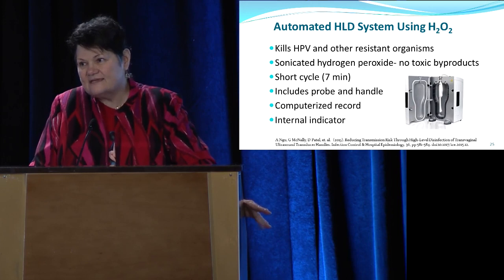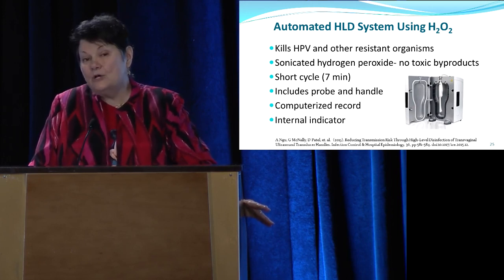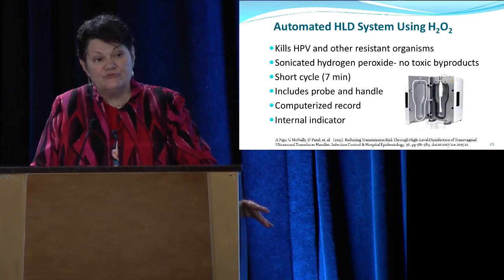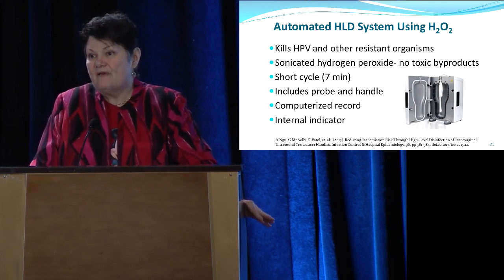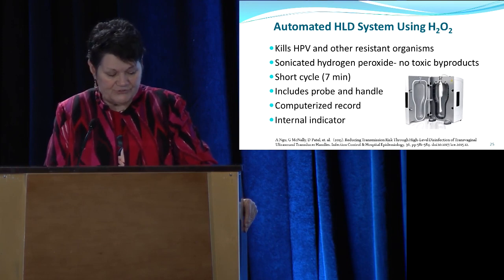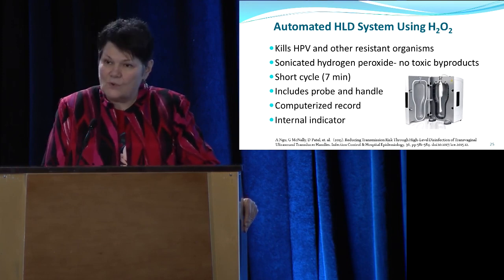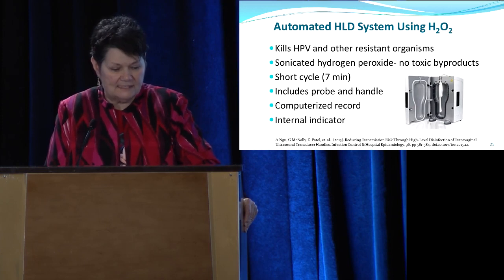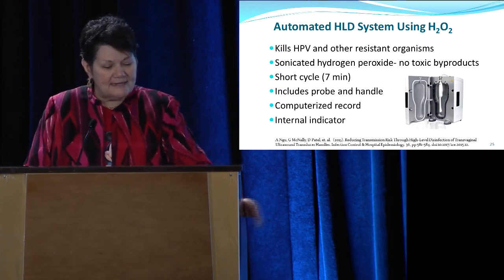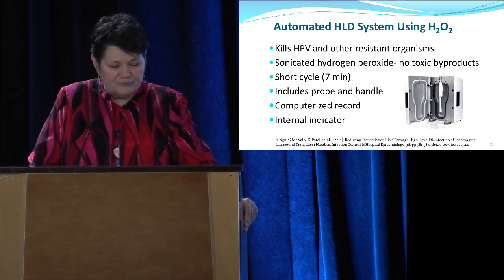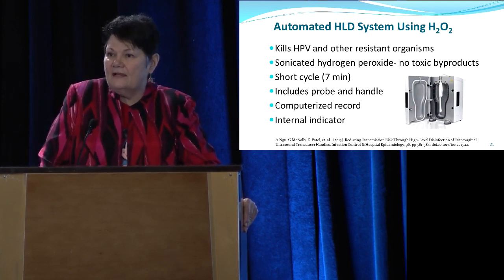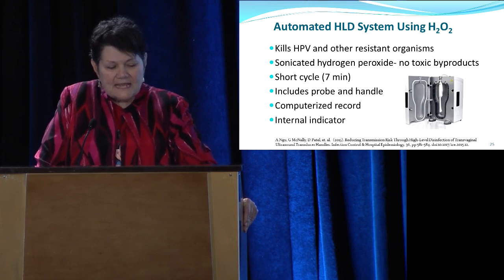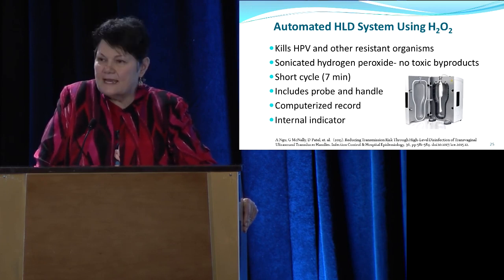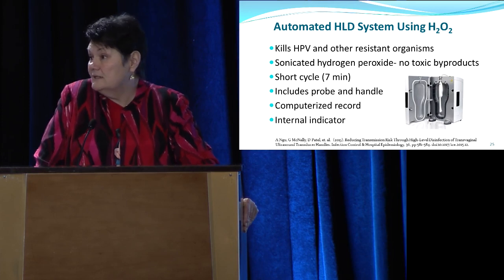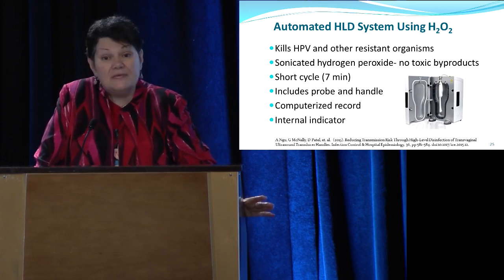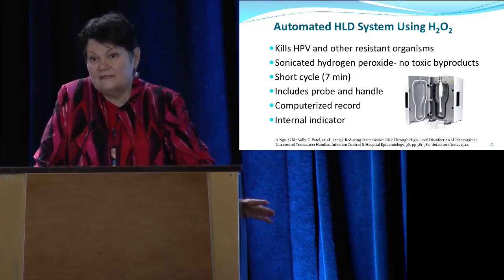The FDA has not taken action yet, but I know in my last facility we switched over to the Recert because we were concerned about that and made sure that we were using something that was safer for the staff as well as effective against some of these other pathogens. So the automated high-level disinfectant systems with hydrogen peroxide kill HPV and other multi-drug resistant organisms. It's a sonicated hydrogen peroxide with no toxic byproducts, and that to me is a plus for the users, because they're not going to get exposed to the fumes and the issues.